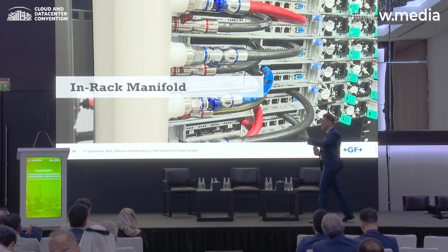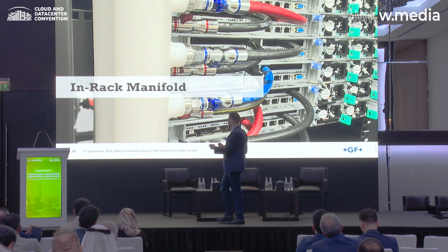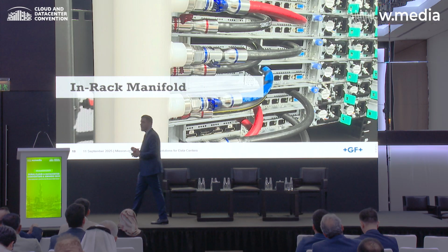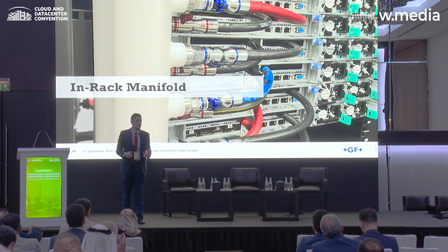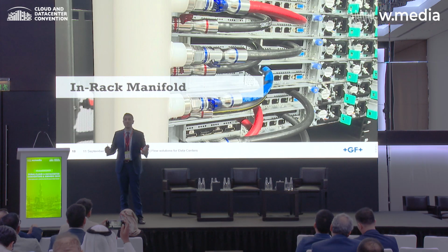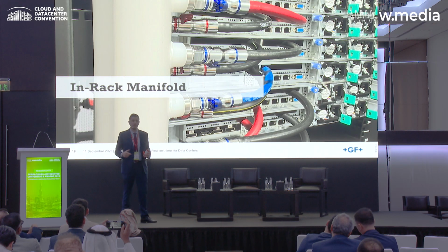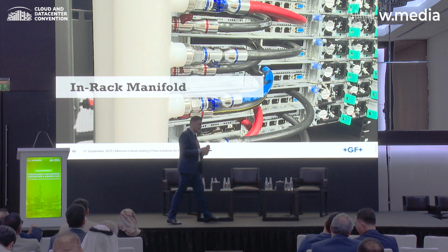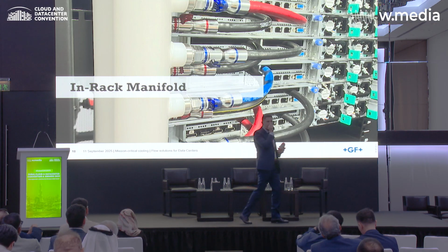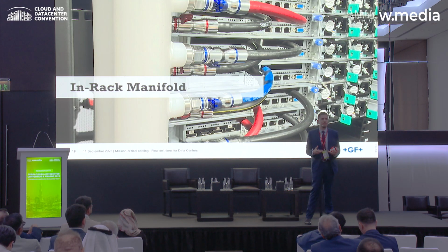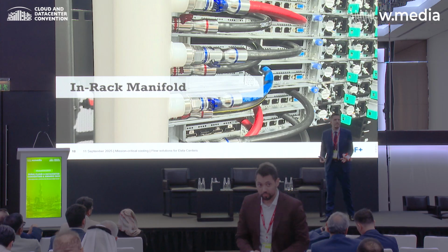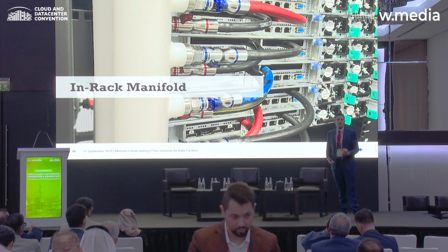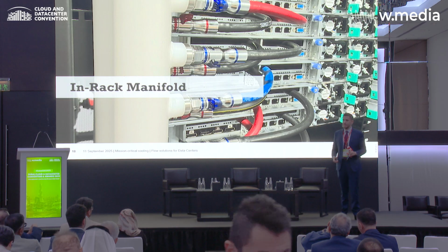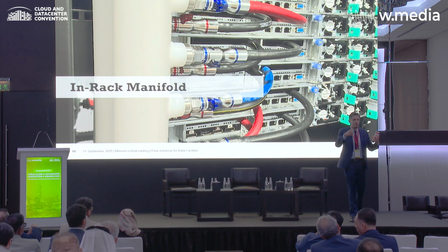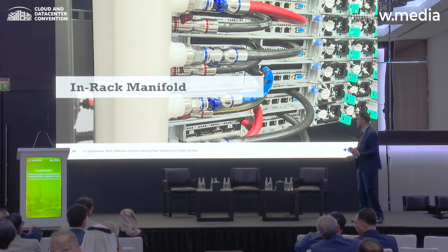The final element would be the in-rack manifold, which at the moment is made with stainless steel, having a quadratic shape. This shape of stainless steel ITE rack manifold causes the fluid to lose its characteristics. At GF, we went back to basics and took it back to its circular shape as a manifold.